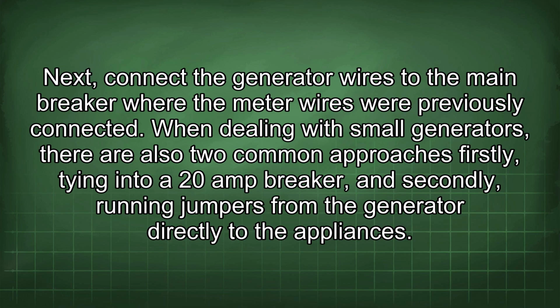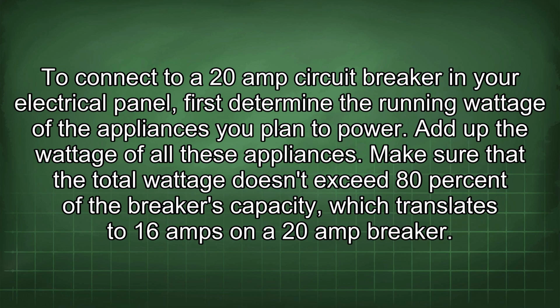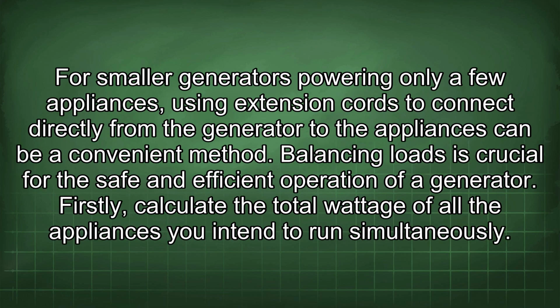When dealing with small generators, there are also two common approaches: firstly, tying into a 20 amp breaker, and secondly, running jumpers from the generator directly to the appliances. To connect to a 20 amp circuit breaker in your electrical panel, first determine the running wattage of the appliances you plan to power. Add up the wattage of all these appliances. Make sure that the total wattage doesn't exceed 80% of the breaker's capacity, which translates to 16 amps on a 20 amp breaker. For smaller generators powering only a few appliances, using extension cords to connect directly from the generator to the appliances can be a convenient method.